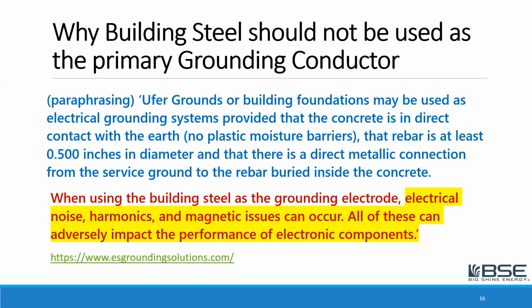So why should building steel not be used as a primary grounding conductor? This company, ES Grounding Solutions, is a company that does grounding surveys, and they install upgraded grounding equipment. And on their website, they put this notice: when using the building steel as the grounding electrode, electrical noise, harmonics, and magnetic issues can occur. All of these can adversely impact the performance of electronic components. So here you can see that there's not supposed to normally be a lot of current flowing through the grounding system, but there will always be a little bit. And when there's a disturbance of some kind, then there will be a little pulse going through the grounding system. But here, that pulse doesn't go directly into the earth ground below the building. It goes up into the steel structure of the building, and that's what this website is referring to. This is not good for electronics.